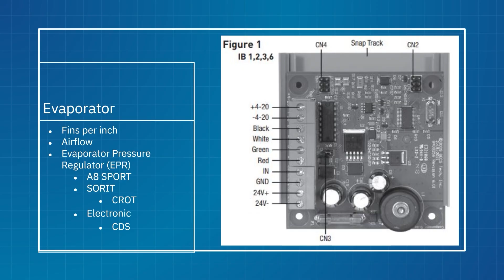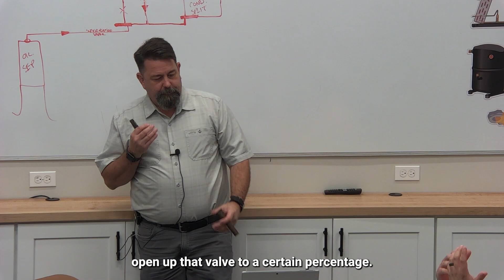Now, here's the other side of it. This is a fairly rare Novar board. We just don't see this very often. Me and Ian ran into this being used completely differently a couple weeks ago. There was a glycol setup that had valves that switched between chillers, open and close the valves, certain percentages. We were using it for that. Like Mason valves? Automatic bypass valves to go from one chiller to another chiller, with the same glycol loop, if the first chiller lost capacity. Depending on the amount of capacity lost, you could open up that valve a certain percentage. So if you lost a couple compressors.